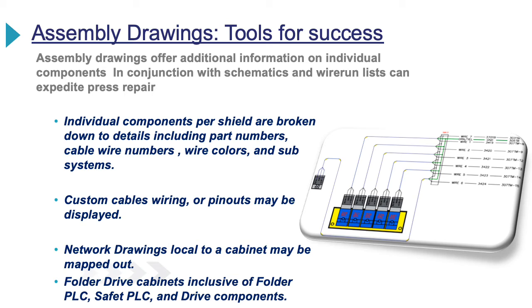Assembly drawings. Assembly drawings are a great tool to get down to the component level. Not only do they show you the actual component, they show you the part number of the component, where it is assigned to in the cabinet. It also shows color coding on some of the wires, the wire numbers, and the wire termination points. These details are important, and many of these are not displayed on the schematics. You should be working hand in hand with the schematics when you're working with the assembly drawings.